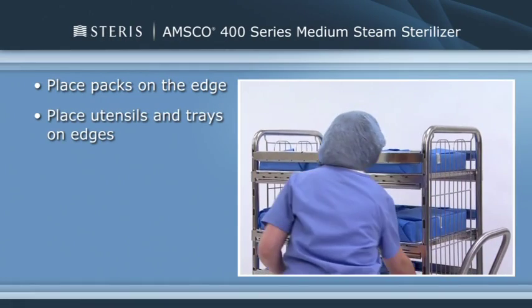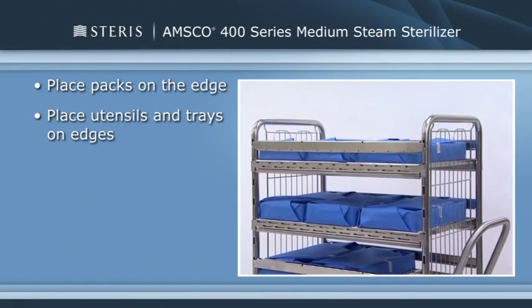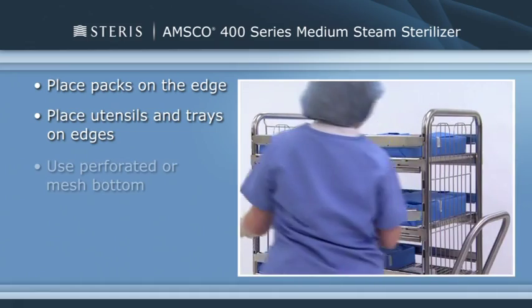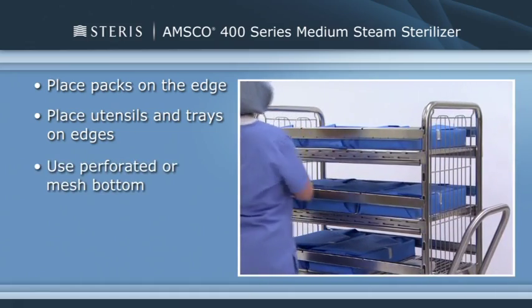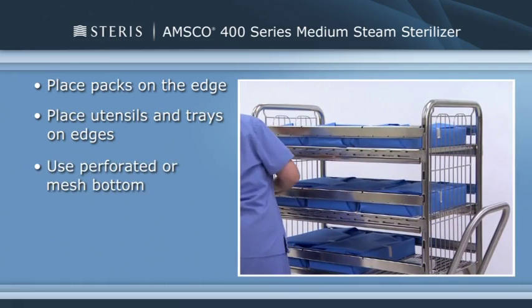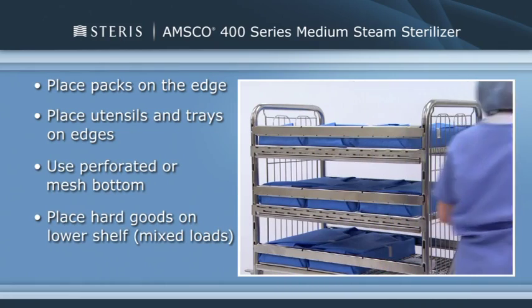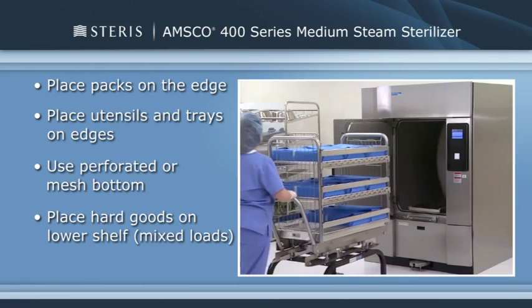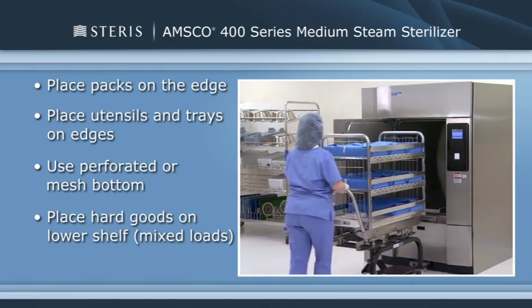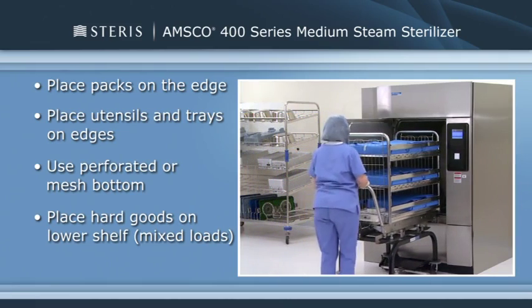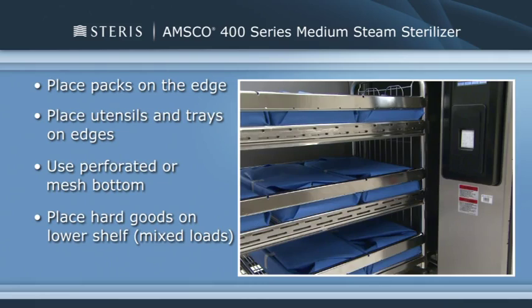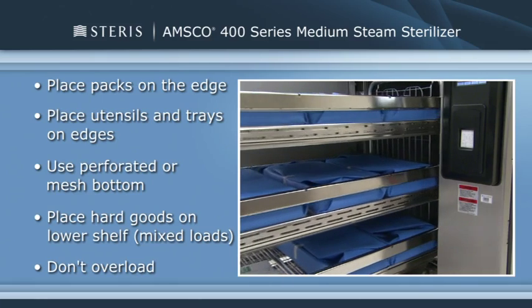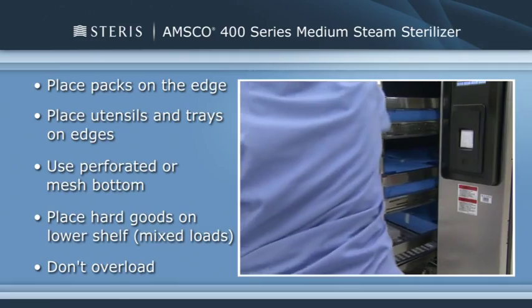Place utensils and treatment trays on their edges so they'll be sterilized and properly dried. Place instrument sets in trays that have a perforated or mesh bottom. Place flat. If mixed loads of fabrics and hard goods, place the hard goods on the lower shelf. This reduces the wetting of fabric packs from condensate dripping from a hard goods load. Be careful not to overload the sterilizer. Allow for steam penetration between packs. Avoid contact with the wall of the chamber.